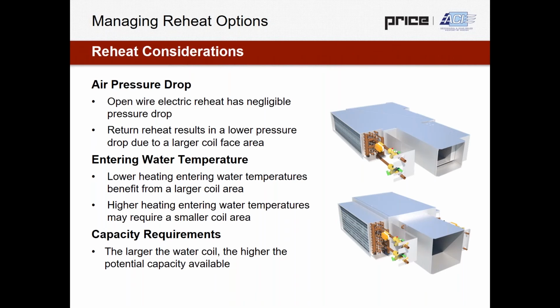Another major consideration here would be the entering water temperature. A larger coil face area is going to be a very large benefit if you have a much lower entering water temperature for heating. I generally like to say, if you're looking at 130, 140 Fahrenheit and down, there's some tangible benefit to being offered a return configuration reheat coil. If you're looking at higher entering water temperatures, 160 or 180 degrees, you might require a smaller coil area to get the leaving water temperatures you want, so maybe in that case you go for a discharge configuration. And then finally, and kind of obviously, what are your capacity requirements? The larger the water coil you can offer, the higher the potential capacity available.